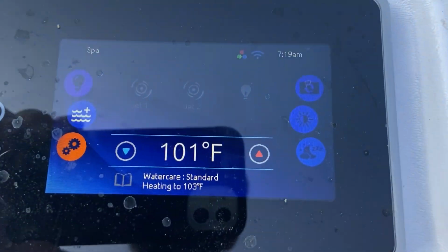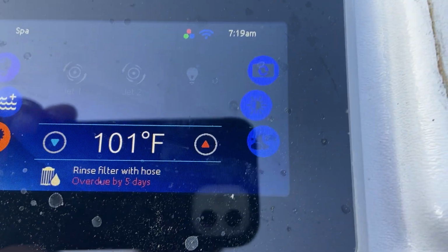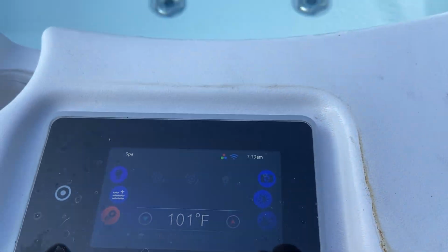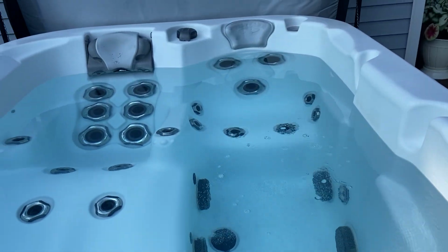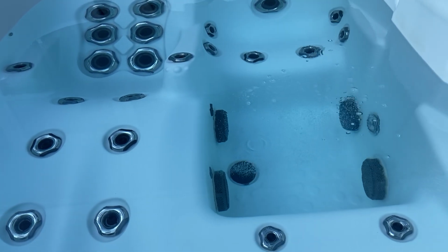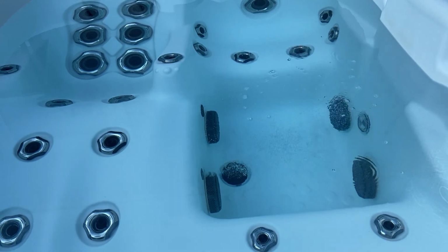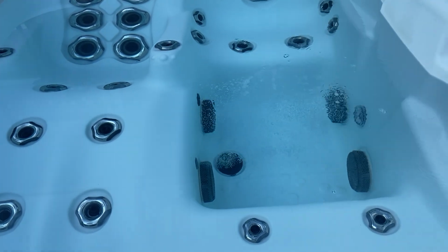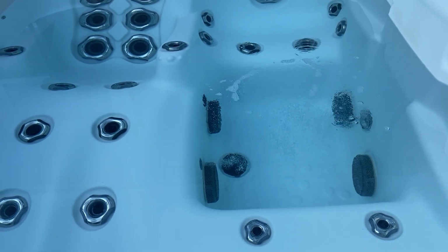So we're gonna go up here, we're gonna find the flow switch, and we're gonna plug it in. Push it in there. I just heard a click. That should be the heater relay clicking. And the error message went away. Okay. So in this case, what we just troubleshot was the flow switch was the issue, right? We tested the flow switch, we jumped across it, we restored flow. It did read adequate flow. The board was not the issue.